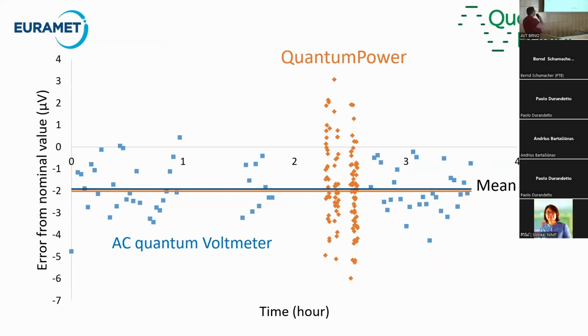Here are some of the actual measurements we have done, comparing our system, the QuantumPower system, with the AC quantum voltmeter from Supracon. Supracon uses a differential method, different from ours, but the object we measure is the same, the Fluke 5720. The AC quantum voltmeter does have smaller errors, but it needs a lot more time to measure compared to the QuantumPower system. They need hours, whereas we need like 20, 30 minutes.